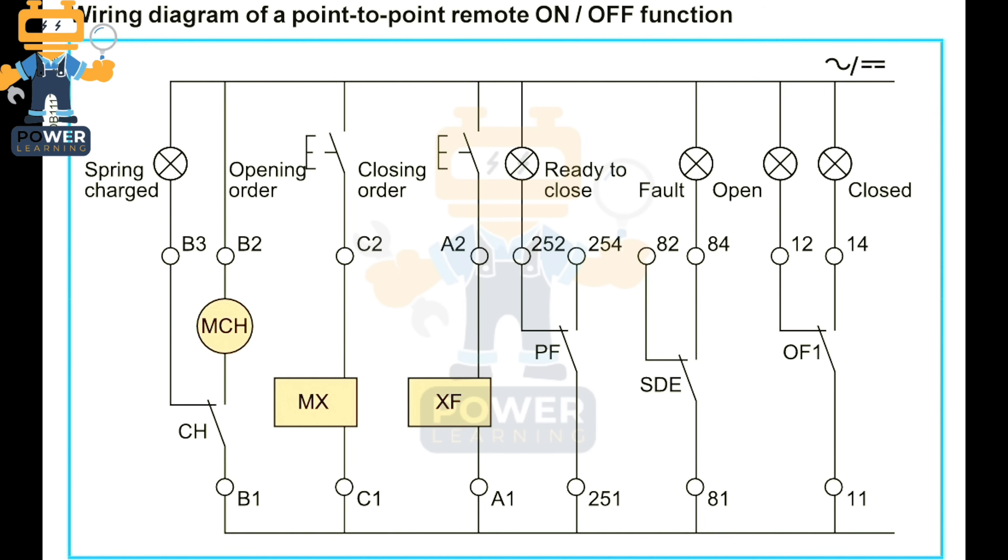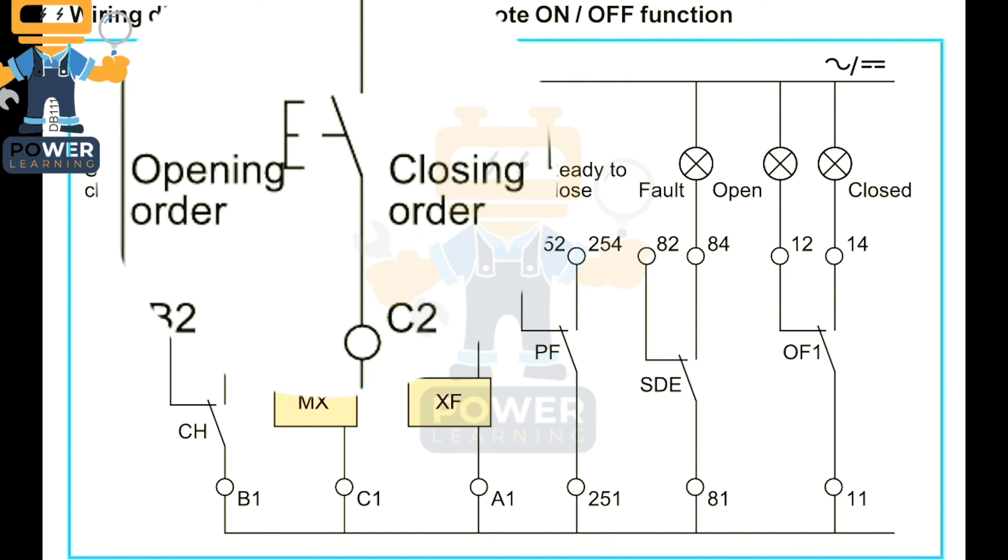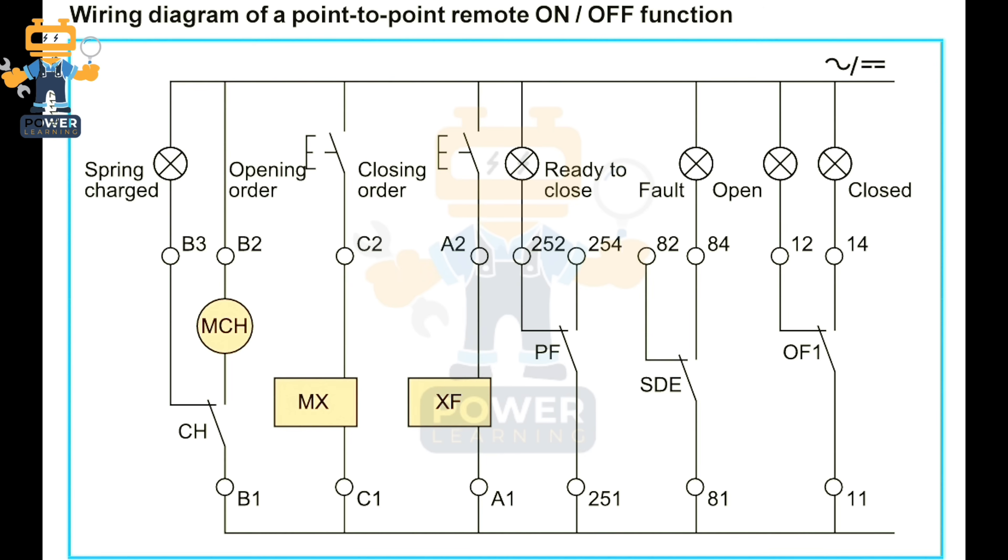After that we will see opening order and closing order. What is meant by opening and closing order? Opening order means to open the breaker, to turn off the breaker, and closing means to turn on the breaker and to close the breaker. It means we need two coils to turn on the breaker and to turn off the breaker. For turning on we need closing order. For turning off we need opening order. The opening order coil is called MX and the closing order coil is called XF.